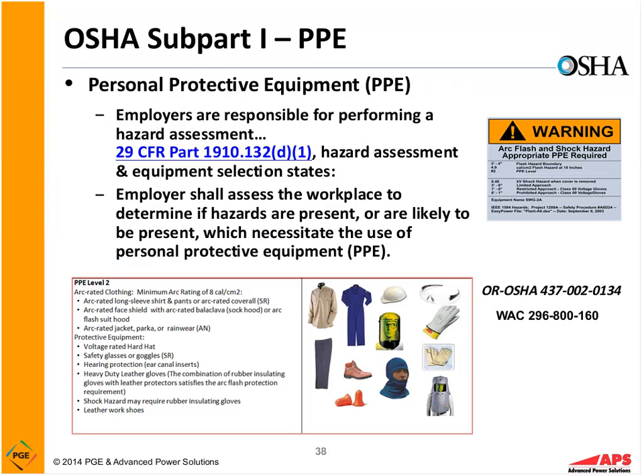When I look at subpart I, personal protective equipment, employers are responsible for performing a hazard assessment. So it states that employers shall assess the workplace to determine if hazards are present or likely to be present, which necessitate the use of PPE. So it's very important that you understand how to assess the hazards, and you do what's called a hazard slash risk assessment, where you're looking at what are the voltages that my folks are exposed to? What is the potential for shock? Is everything covered up? What is the energy level in that cabinet or in that electrical switchgear? What type of PPE do they need to wear, or what do they need to do to protect themselves to avoid even the exposure to this type of hazard? These are all things when we look at the hazard assessment and the risk assessment.